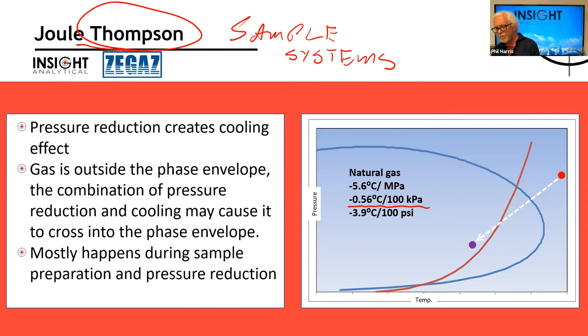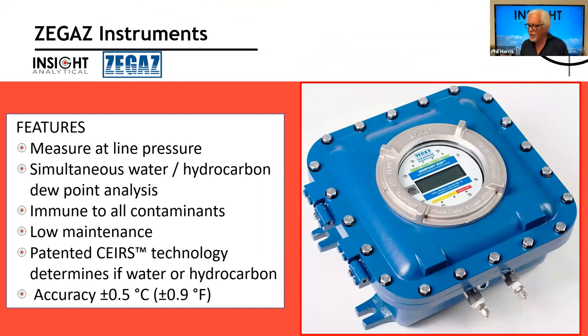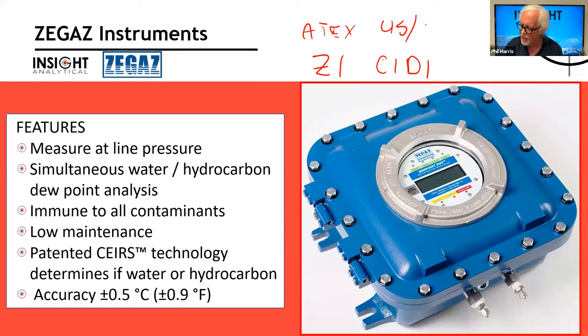So one of the ideal things would be an analyzer that started off at a warm temperature, cooled down to a cooler temperature while the whole system's under pressure, and then we could monitor the dew points. So the ZEGAZ device is available. It is an ATEX Zone 1, CSA FM Class 1 Div 1 package, sort of for the US and Canada. In the US you mostly still use the division system. Canada has moved a lot over to the zone system now as well. So for Canada it's Div 1 Zone 1, and it's available for European IEC ATEX Zone 1.